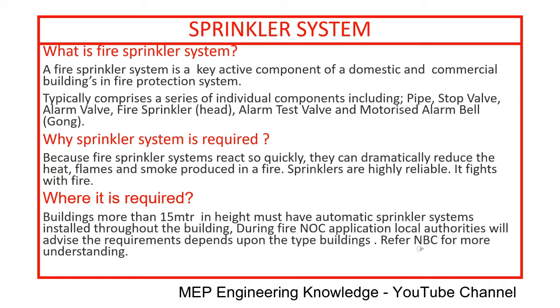Why is a sprinkler system required? Because fire sprinkler systems react so quickly, they can dramatically reduce the heat, flames, and smoke produced in a fire. Sprinklers are highly reliable. It fights with fire where it is required. Buildings more than 15 meters in height must have an automatic sprinkler system installed throughout the building. During fire NOC application, local authorities will advise the requirements depending upon the type of building. Refer NBC for more understanding.